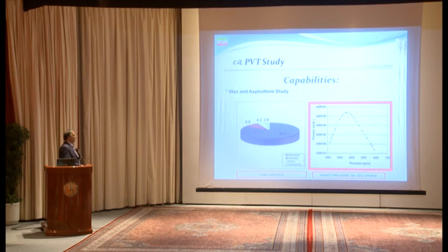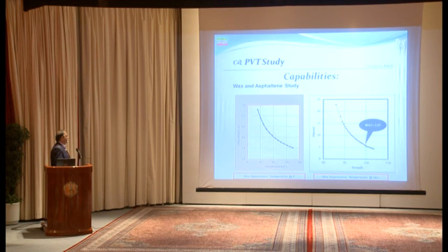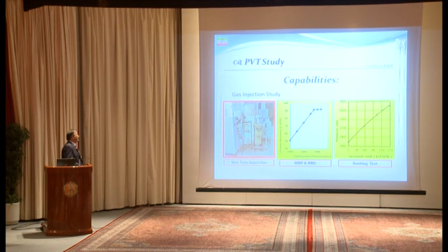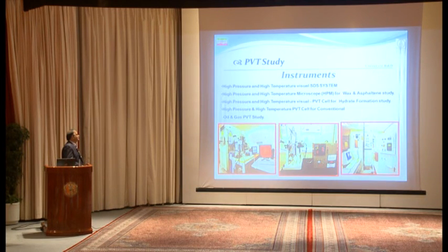This curve shows us the power versus pressure of the laser beam during the PVT, during the pressure drop. You can obtain the onset pressure and also viscosity versus temperature. Measurement of viscosity versus temperature is used for wax appearance temperature.